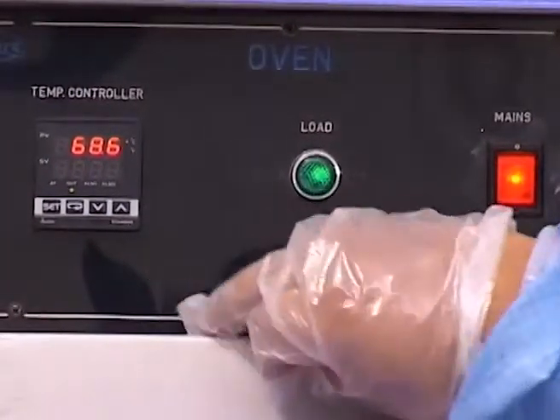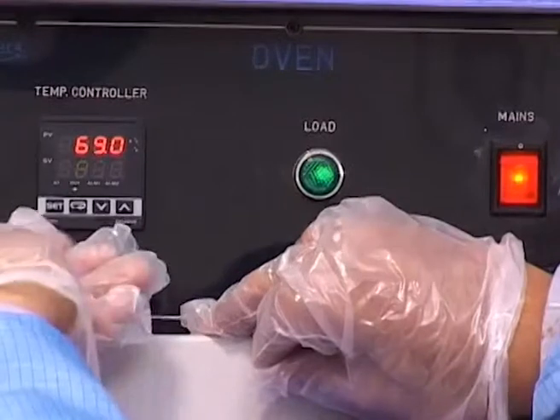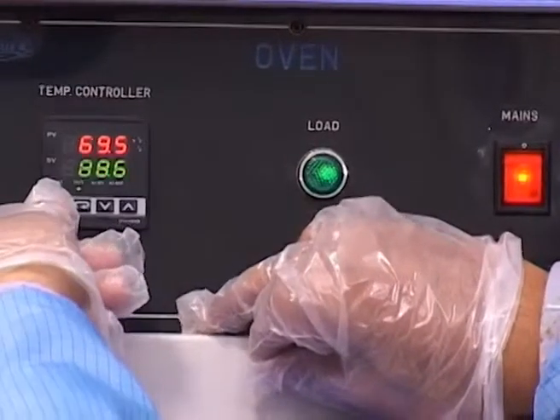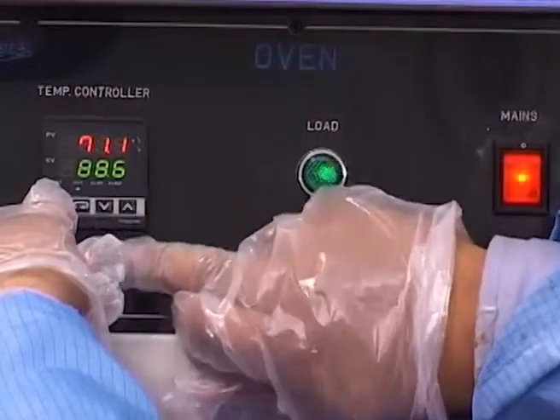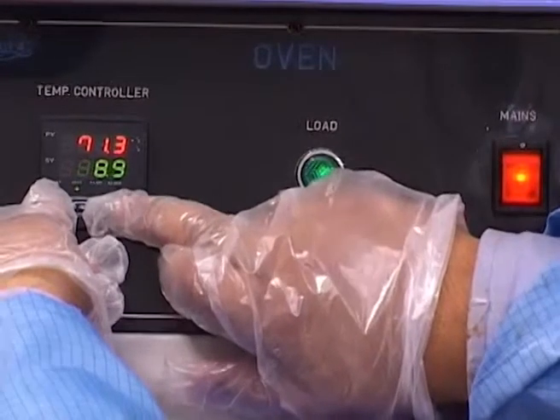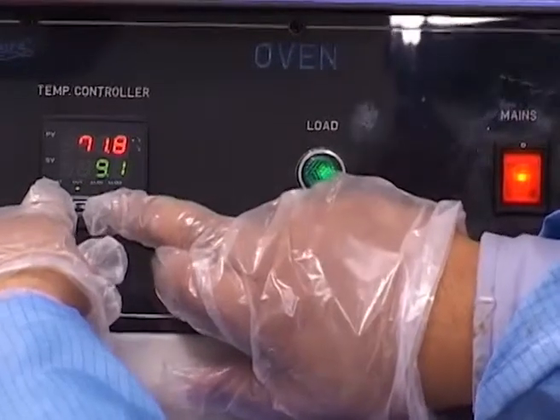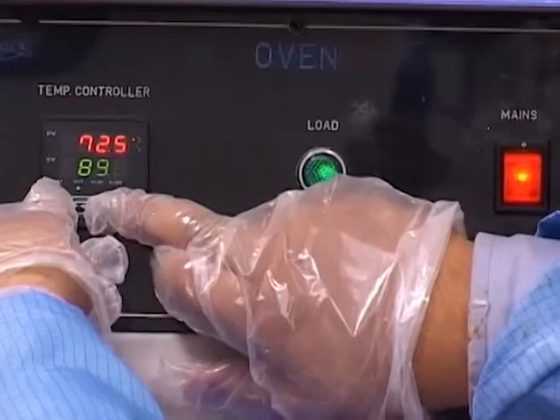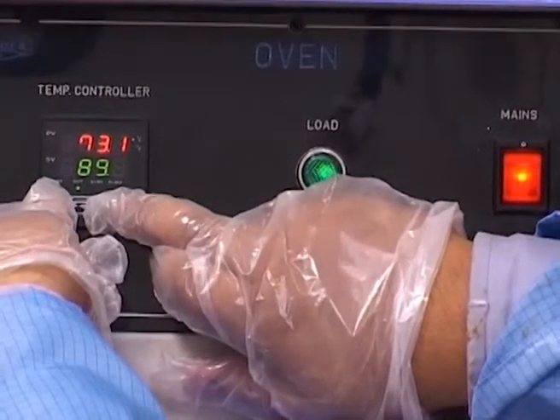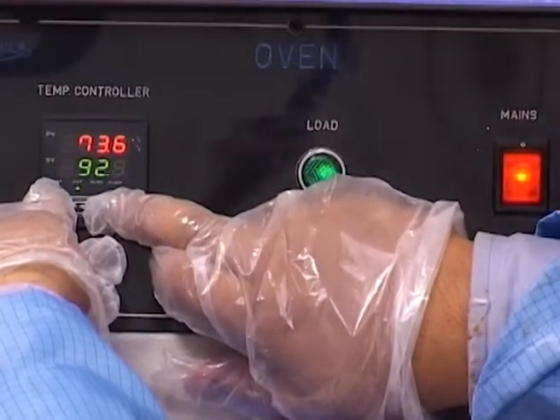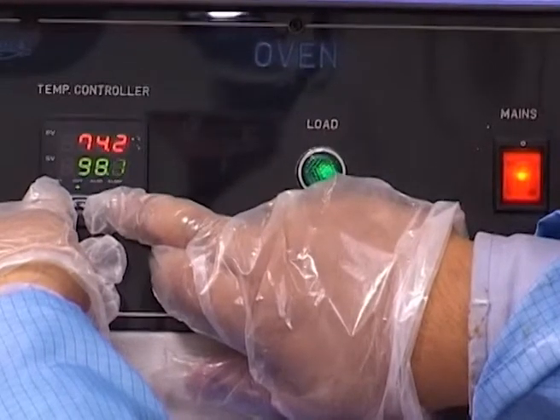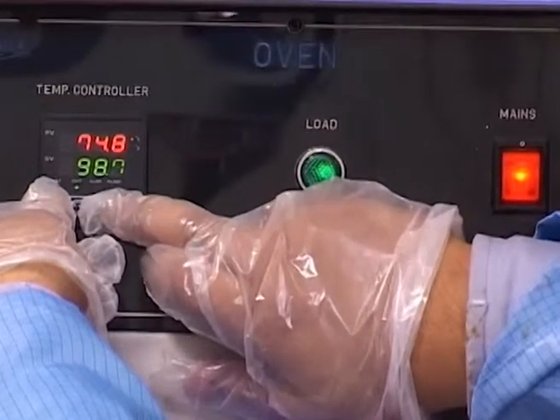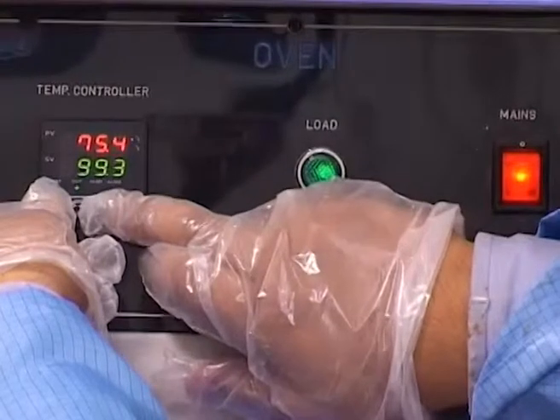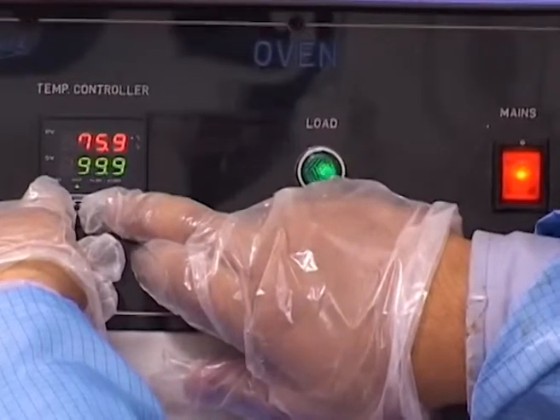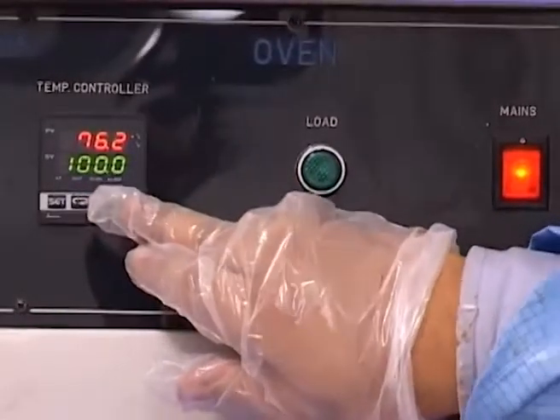In order to control this, if you can see here, there is a set option. So you press the set option and then take the up arrow or down arrow. As you are seeing in the figure here, the SV, or the set value, is varying: 89.3, 89.4, 89.5, 89.6, and so on. We take this all the way to about 100 degrees, which is important for proper dehydration of the wafer surface. And once you reach 100, you leave the set key, and this is now set at 100 degrees.